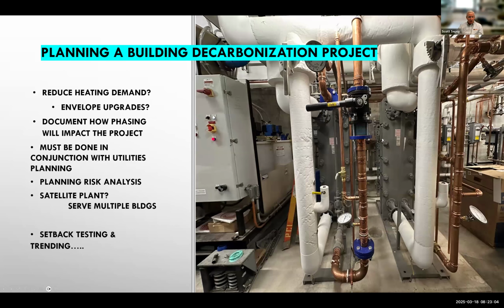The next, so also more factors to consider. Can you reduce the demand through maintenance and energy projects? Can you use low flow fume hoods, upgrade vivarium controls? Even simple things like door or window upgrades or seal improvements that can reduce parasitic infiltration loads can be useful. Phasing is something to consider closely.